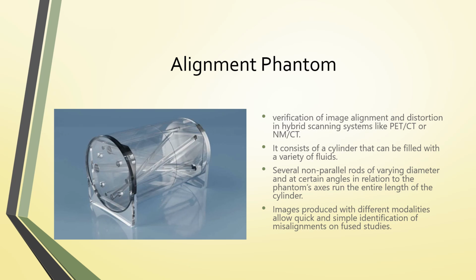This is an example of an alignment phantom. It's used for verification of image alignment and distortion in PET-CT systems. It consists of a cylinder that can be filled with a variety of fluids, and then several non-parallel rods that have varying diameters. As you can see on the end here, each one of them is a different size, and at certain angles in relation to the phantom's axes, they run the entire length of the cylinder. Images are produced with different modalities to allow quick and simple identification of misalignment in fused studies.